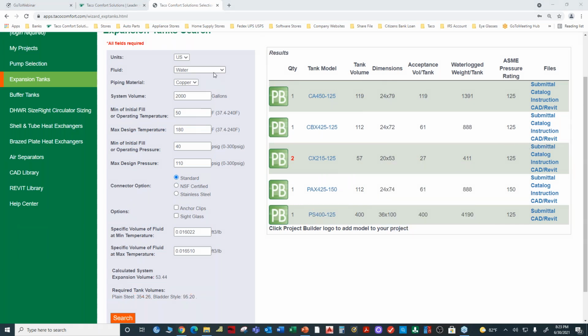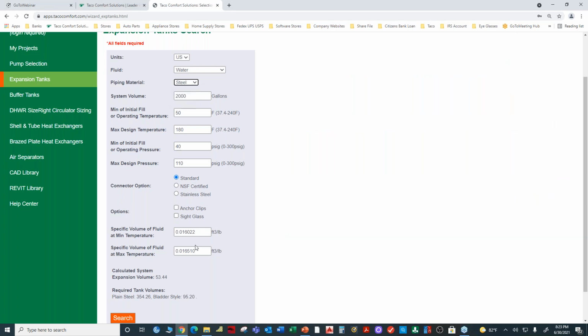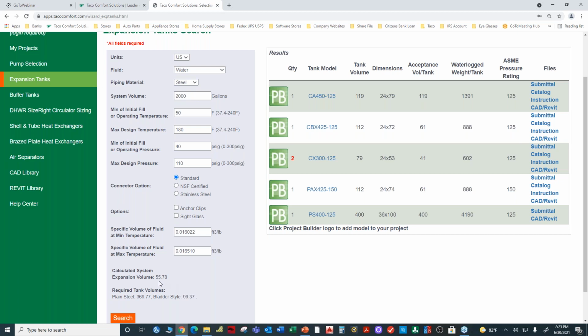There we go. And if you'll notice, I take credit for the copper, and if I change that to steel, look what happens when I click on search. It goes from 53.44 gallons to 55.78 gallons. That's because steel does not expand as much as copper. So if I'm using a plastic material, the plastic material typically expands more than copper. But to be conservative, I could use either steel or copper.